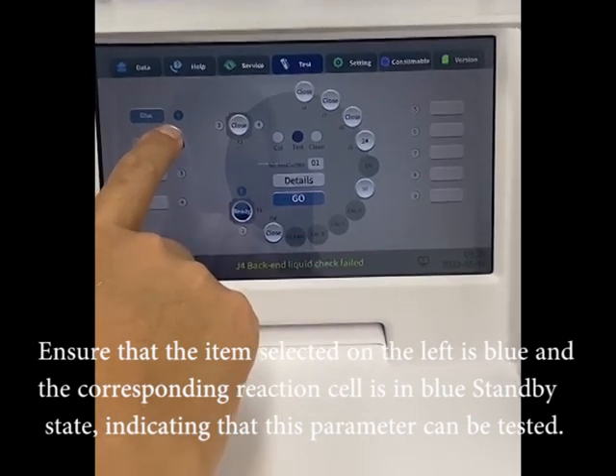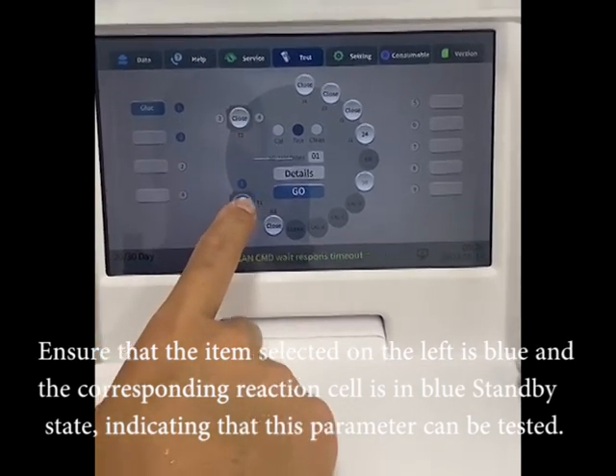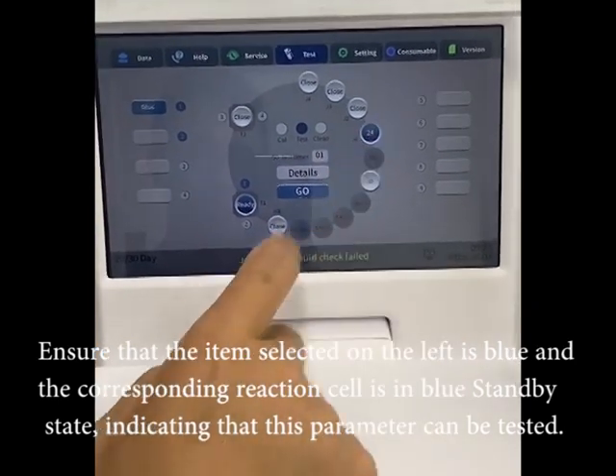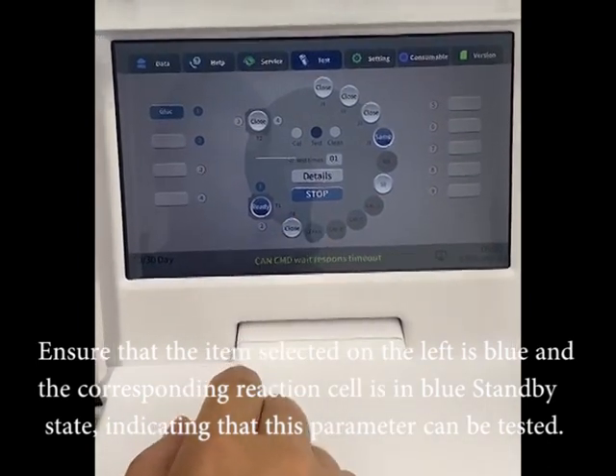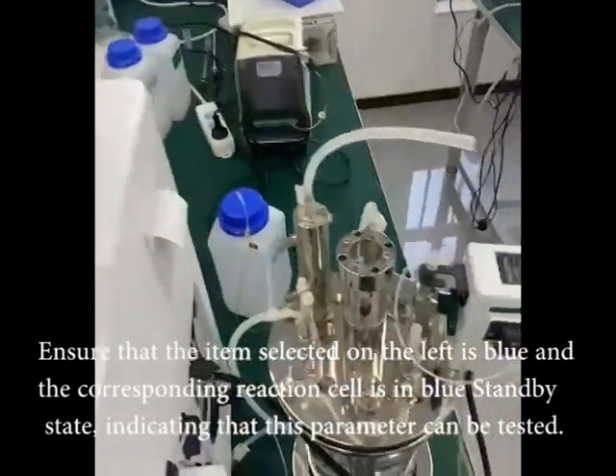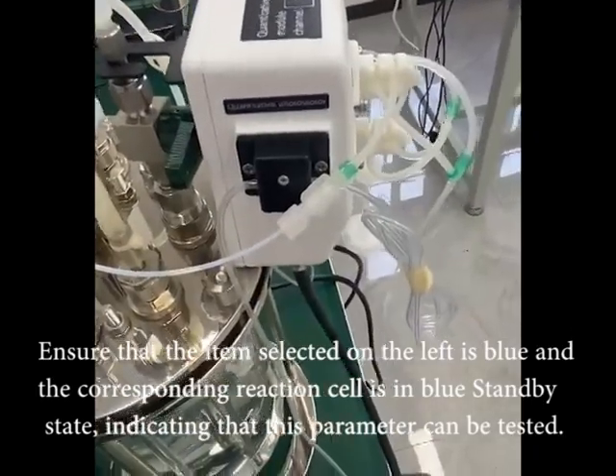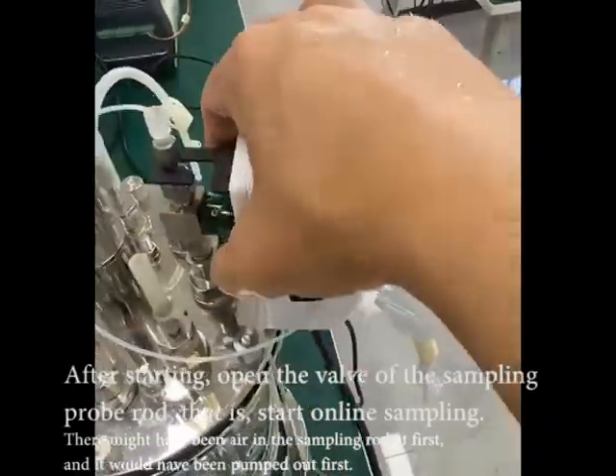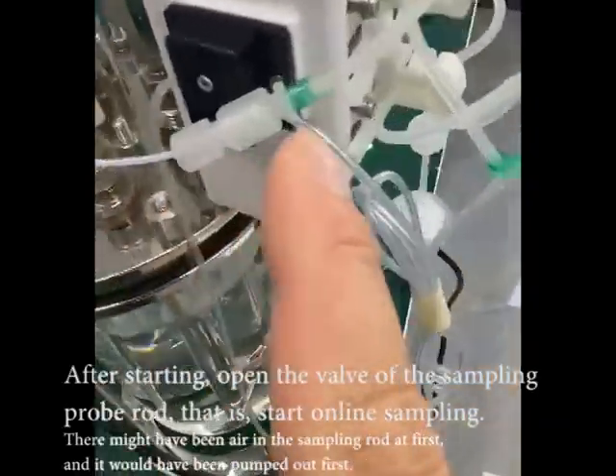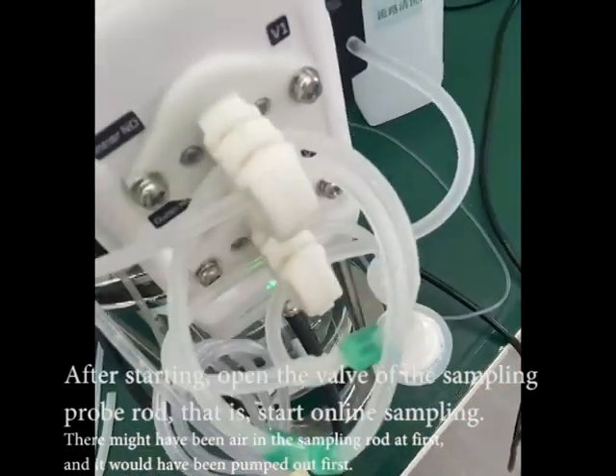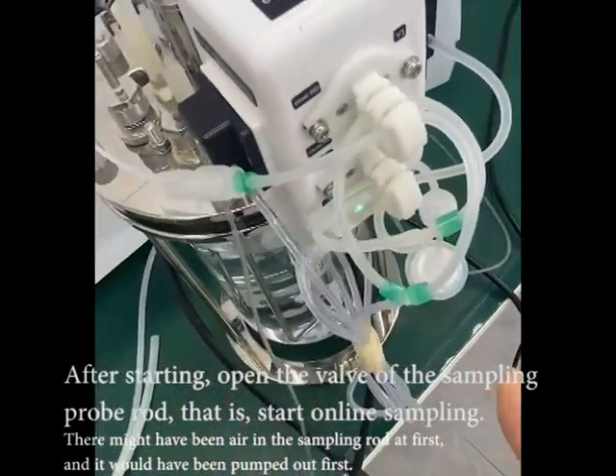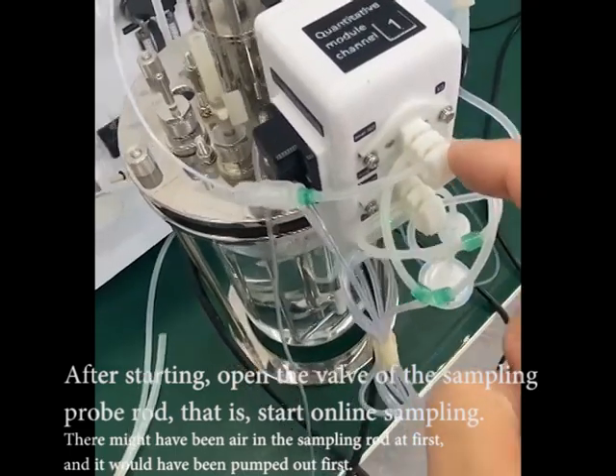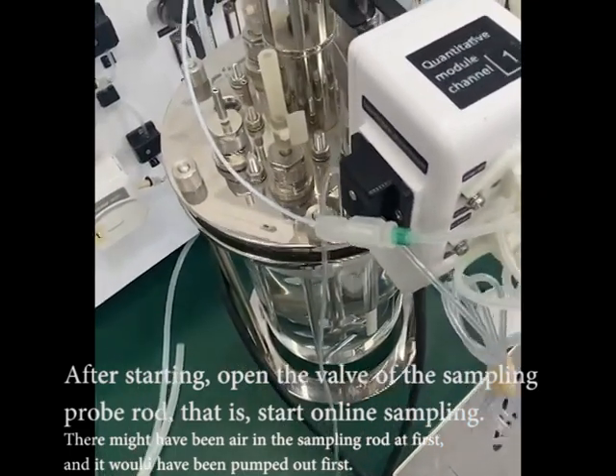Ensure that the item selected on the left is blue, and the corresponding reaction cell is in blue standby state, indicating that this parameter can be tested. After starting, open the valve of the sampling probe rod, that is, start online sampling. There might be air in the sampling rod at first, and it will be pumped out first.